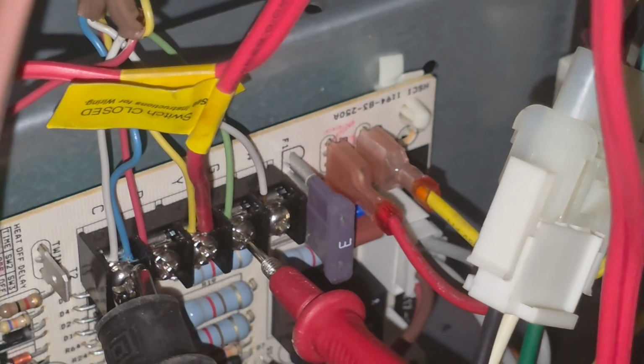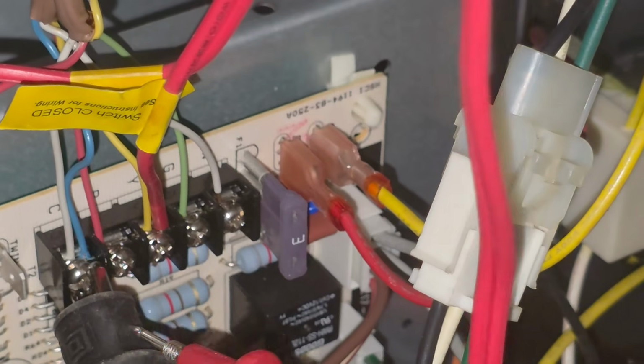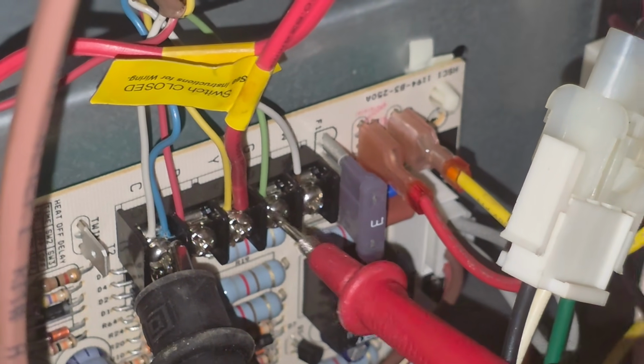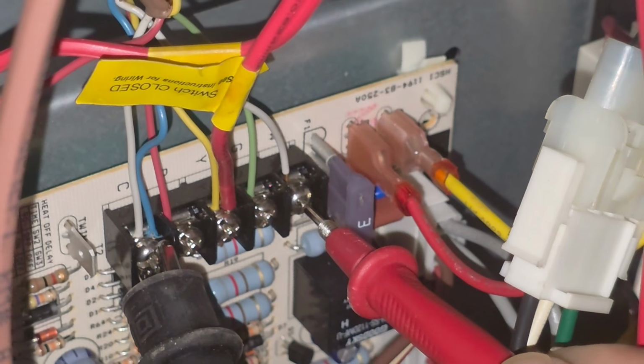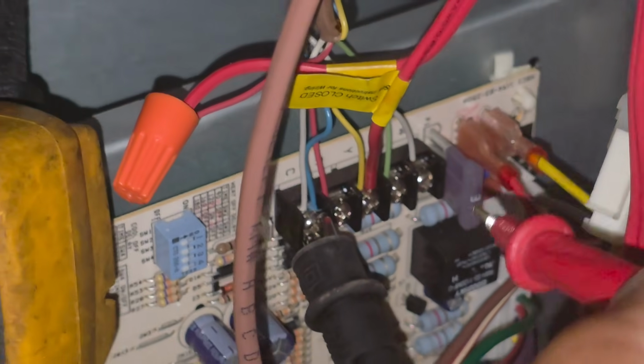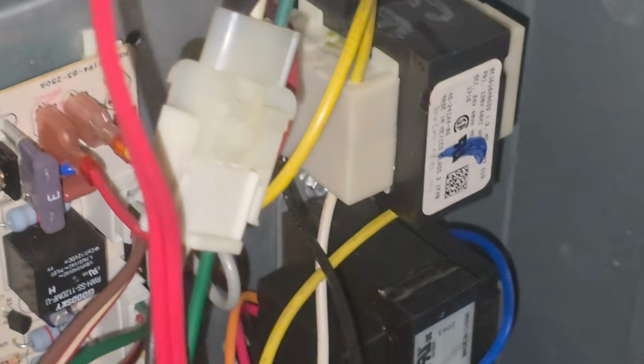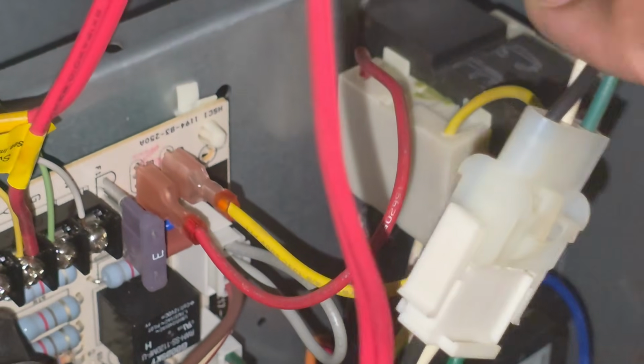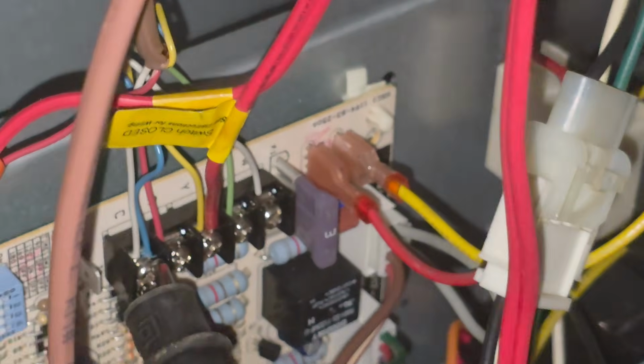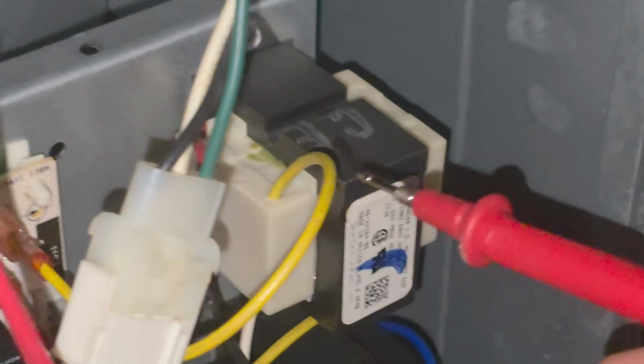Let's go back over to my, still pivoted. Still got my pivot foot, I'm good. Not a violation. I go to W1 and I got 26 volts. So I'm just going surgical really with this right here. You see this, this my transformer right here. The transformer, yellow and red.